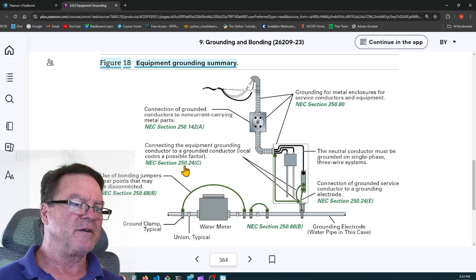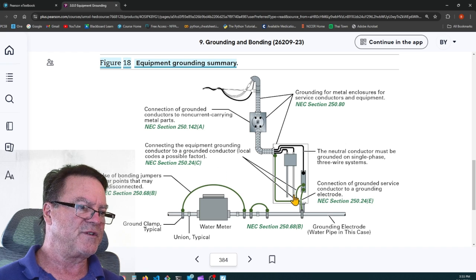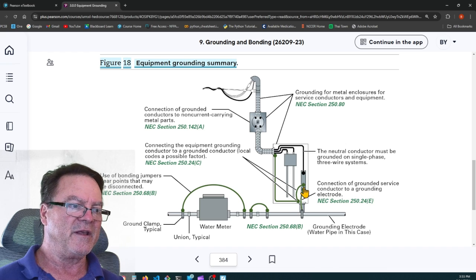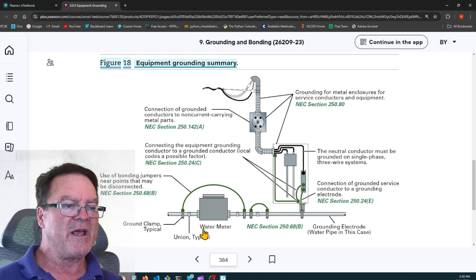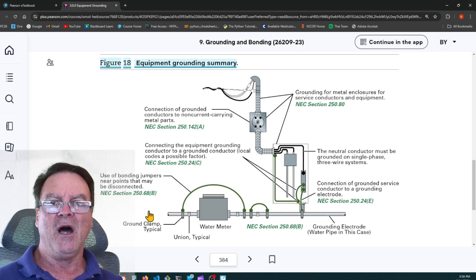a possible factor. It's Article 250.24C, which basically says that the main bonding jumper is going to join the grounded conductor with the equipment grounding conductors and the grounding electrode conductor. That's, of course, the main bonding jumper. And the use of bonding jumper near points that may be disconnected, 250.68B. This is why we cannot use the water pipe as the sole means of ground.